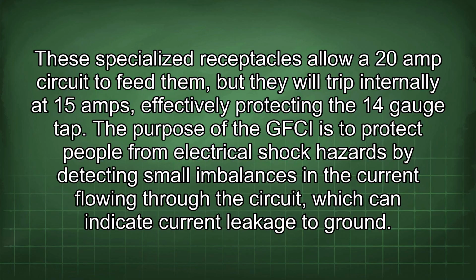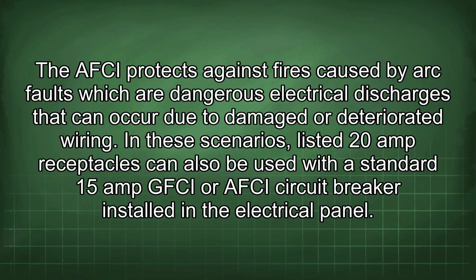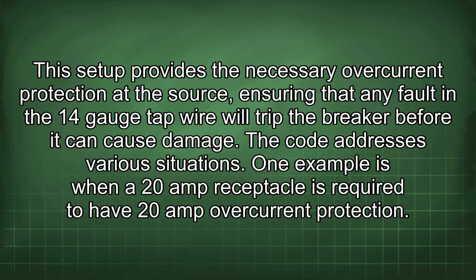in the current flowing through the circuit, which can indicate current leakage to ground. The AFCI protects against fires caused by arc faults, which are dangerous electrical discharges that can occur due to damaged or deteriorated wiring. In these scenarios, listed 20-amp receptacles can also be used with a standard 15-amp GFCI or AFCI circuit breaker installed in the electrical panel. This setup provides the necessary overcurrent protection at the source, ensuring that any fault in the 14-gauge tap wire will trip the breaker before it can cause damage.